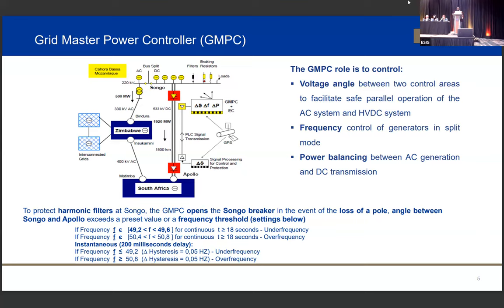One of the limiting factors of the grid power control is whenever frequency deviates by plus or minus 0.4 hertz, the GMPC saves the harmonic filters by opening the bus coupler. That happens after a delay of about 18 seconds. And if it deviates by 0.8 hertz, it opens the bus coupler with a delay of about 200 milliseconds.